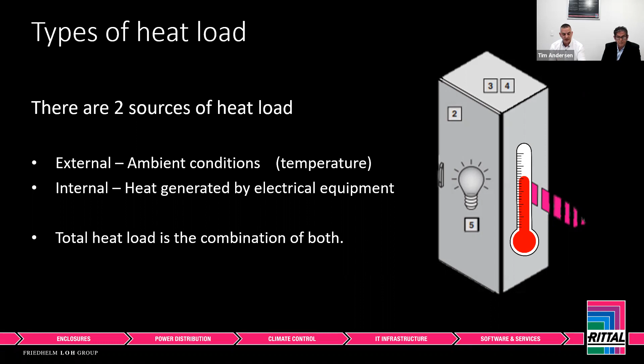So a little bit more about internal heat load. Our practical approach in determining the internal heat load value is to examine each and every electrical component. Getting values from manufacturers' data sheets is a straightforward method in finding this. Adding up all the component values will give you your total internal heat load. If exact parts are not known, using data sheets for similar products is also a good start.